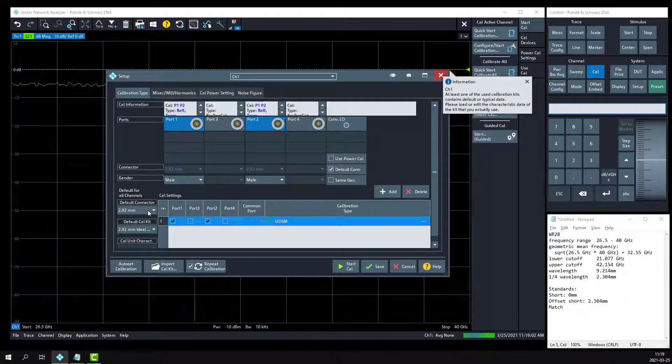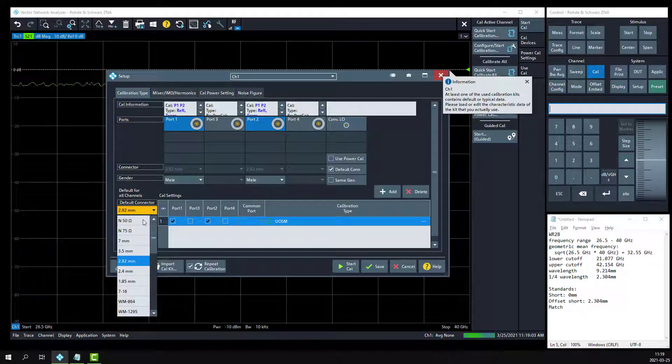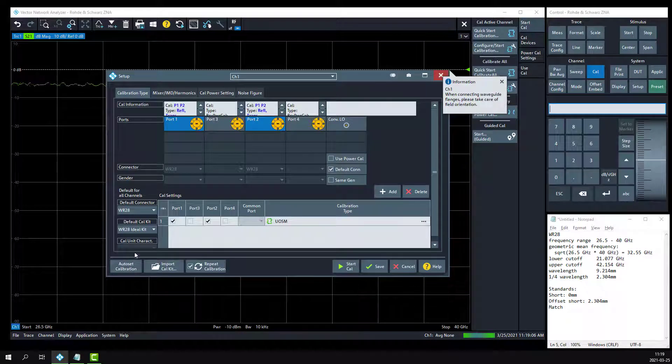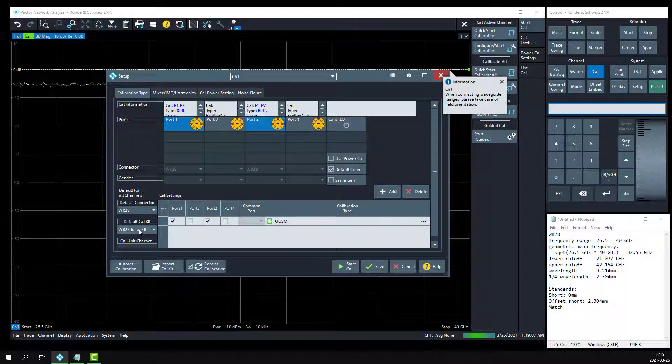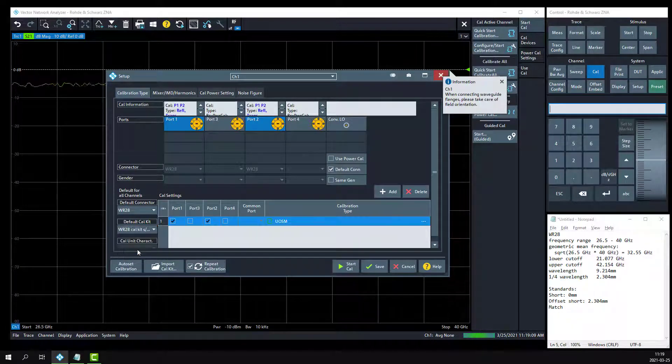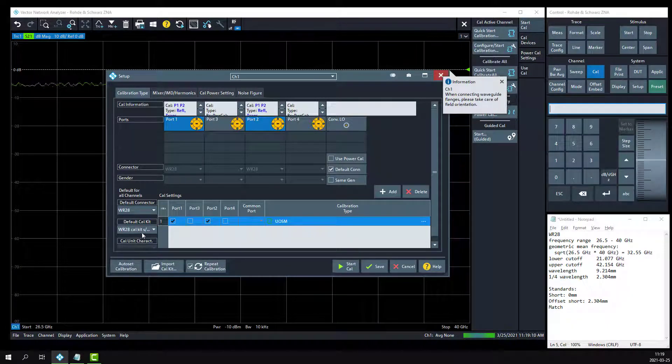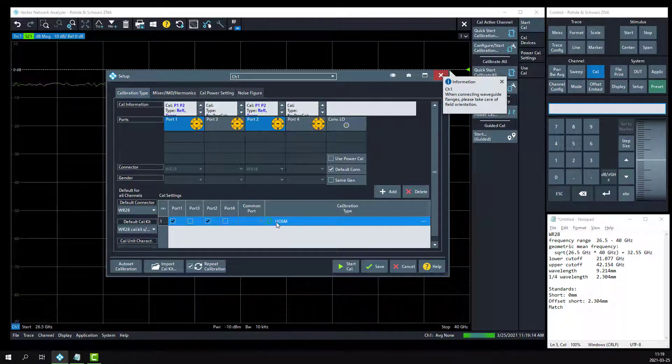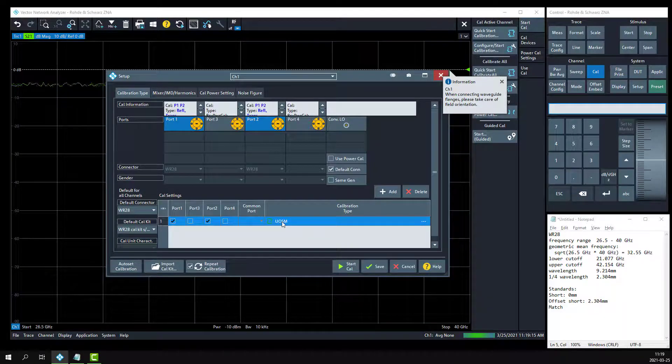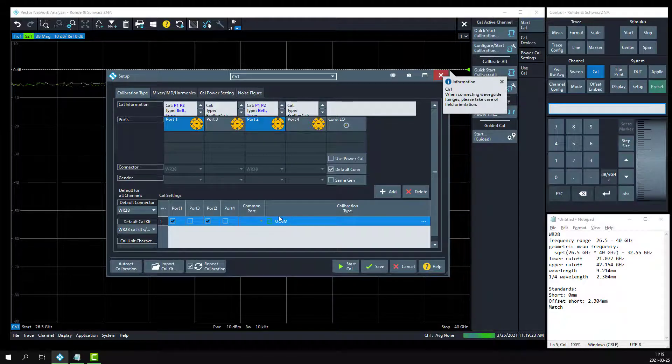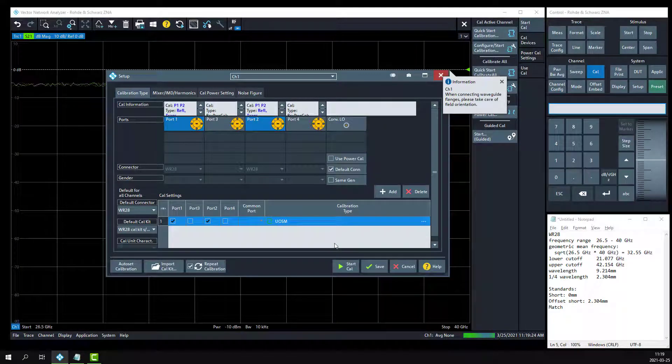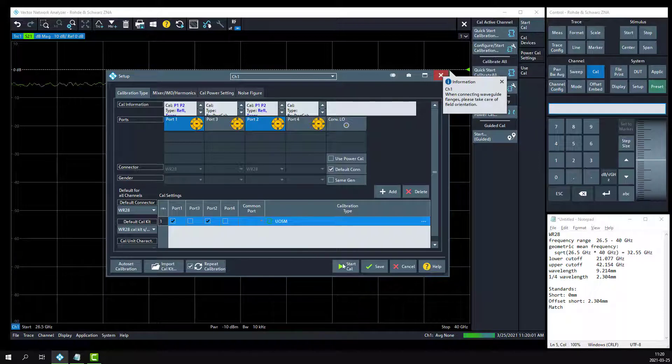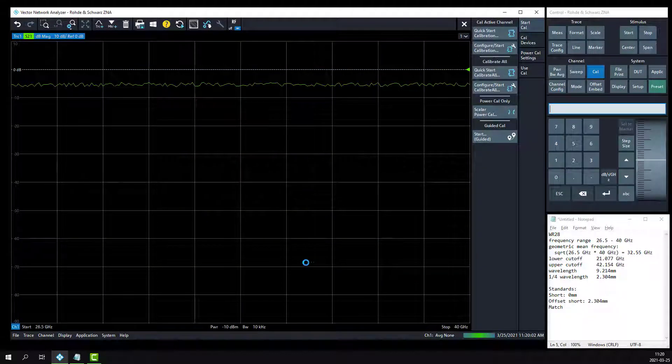We'll change the default connector type to WR28. And we'll change the default cal kit to the cal kit that we just created, cal kit serial number 1. We're going to calibrate port 1 and port 2 using a UOSM calibration type. That is the unknown through open short match technique using the standards we just defined. Click the start calibration button.